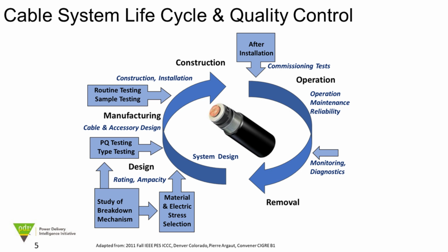Unless that asset is damaged in some way, and we'll talk about what the flags are for a system that's been changed somehow by an extreme event, there's really no reason to take another look at that, because these materials are so stable within the environment. Unless they've been impacted by some major event, they're not going to change condition by themselves. This old thought that somehow the materials are just falling apart sitting there is really more of an overhead mentality. These materials, provided they're installed properly and handled and operated properly, have no reason to just start falling apart. The science is stable.